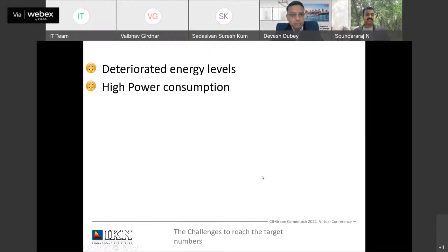The challenges to reach the target numbers are deteriorated energy levels. It means the reduction of secondary air and tertiary air temperature over the period of time, increased vent air temperature, more clinker temperature, and increased power consumption of the cooling fans. So balancing WHR and recuperation is a very challenging task under present operating conditions.